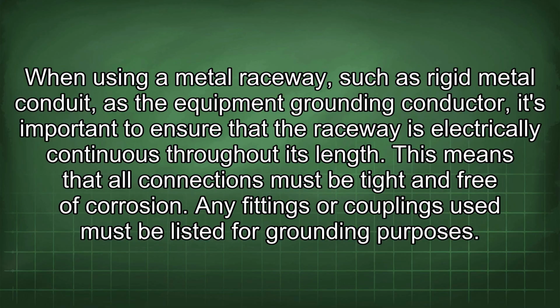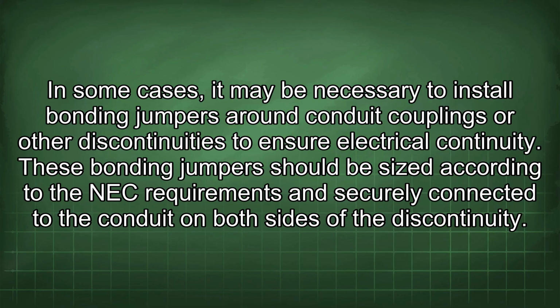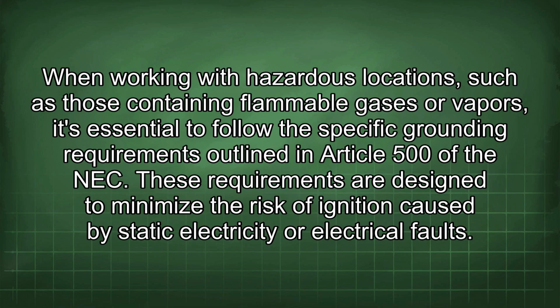Any fittings or couplings used must be listed for grounding purposes. In some cases, it may be necessary to install bonding jumpers around conduit couplings or other discontinuities to ensure electrical continuity. These bonding jumpers should be sized according to the NEC requirements and securely connected to the conduit on both sides of the discontinuity. When working with hazardous locations, such as those containing flammable gases or vapors, it's essential to follow the specific grounding requirements outlined in Article 500 of the NEC. These requirements are designed to minimize the risk of ignition caused by static electricity or electrical faults.